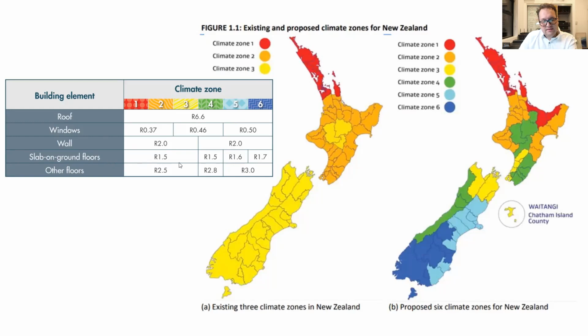The funny thing is, what should be mandated is edge slab insulation, because 80% of the heat is actually lost through the edge. That's the bit that's exposed to the elements. When it's -3 degrees outside and it's blowing wind, it's just the edge that's exposed, and that's just sucking heat away. Doesn't really matter how much insulation you put under it. You could put massive polystyrene pods under your house with added polystyrene under the footings, and it's not going to make much of a difference compared to the edge insulation.